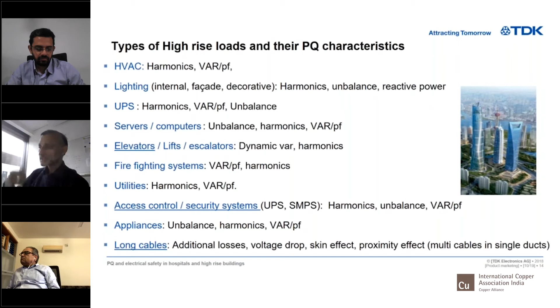And some of these protective devices are very simple, low-cost devices like RCDs, ELCBs, MCCBs, even the right rating of the fuses. And fuses are something we never select properly. And with some of the fuses, because of fear of nuisance tripping, you might as well put a copper bus bar there. The building fire will melt it down, but not an overcurrent. These are very small things, a few dollar fuse, but if it's not correctly selected, it can be a major disaster.